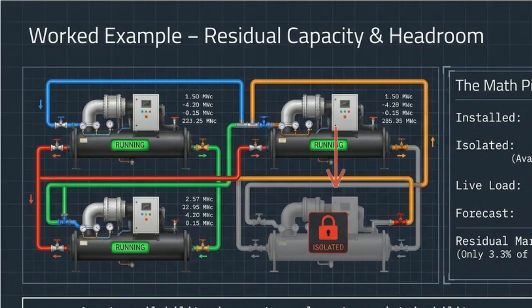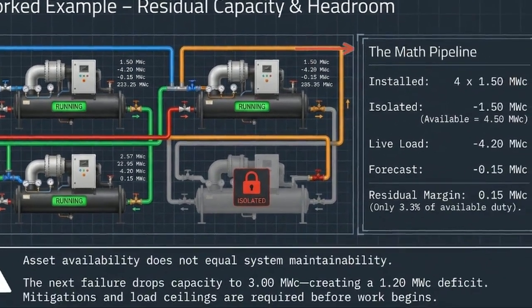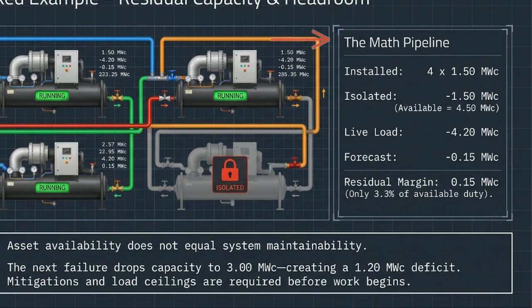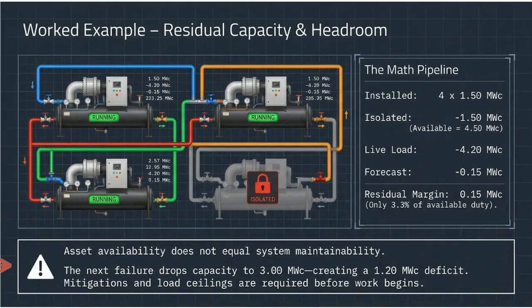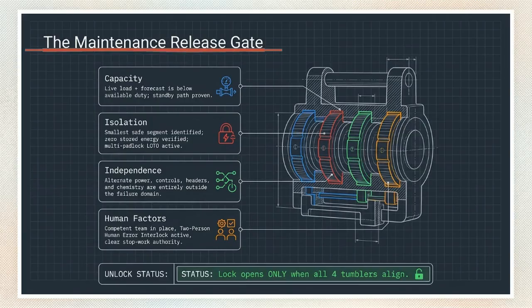Before taking any equipment offline, operators must mathematically prove the residual capacity margin. The calculation in the math pipeline box proves this point. You take the total installed duty, subtract the isolated asset, and subtract the live load forecast. Here, that leaves a razor-thin residual margin of exactly 0.15 megawatts. If the next credible failure drops capacity further, it creates a 1.2 megawatt deficit. Mitigations and strict IT load ceilings must be established before maintenance work begins. To enforce these limits, facilities use a maintenance release gate.